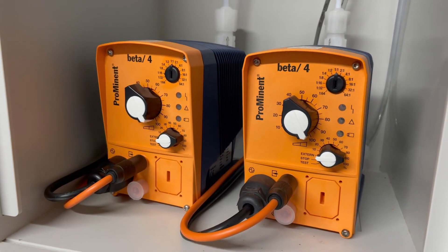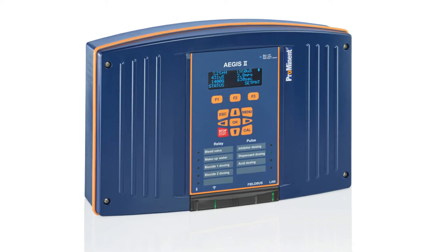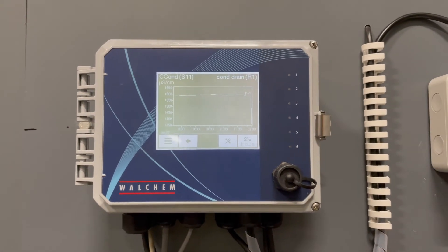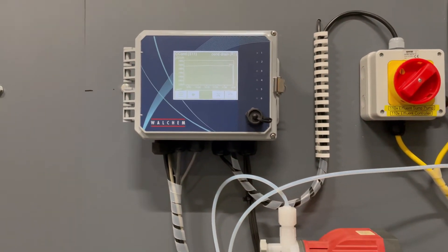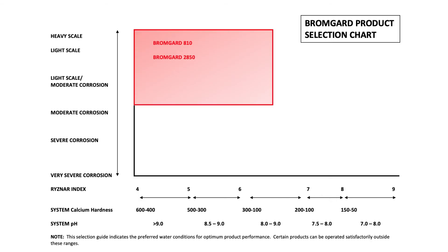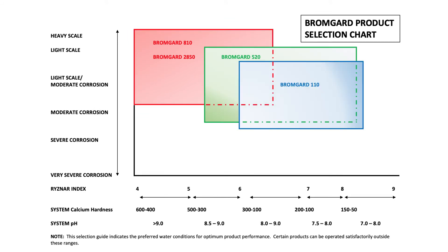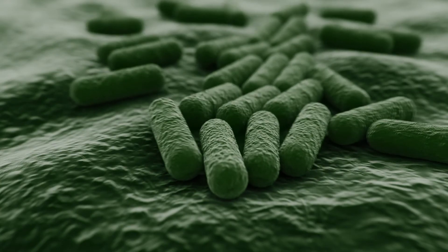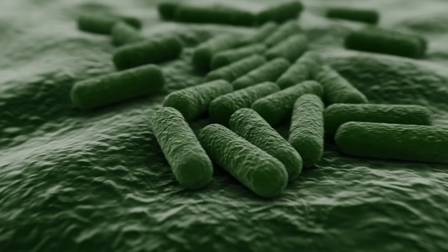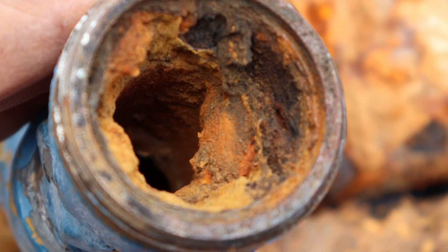Packaged dosing systems such as the Coolplex concept or controllers such as LTH, Prominent, Walchem and many more are ideal means of treatment using Bromgard chemicals, which can fit into most existing dosing setups. Because no two systems or water supplies are the same, the precursor will be specifically chosen depending on the water chemistry specific to that system. This ensures both bacteriological control including Legionella bacteria and effective protection against corrosion and scale to increase performance and longevity of the system.